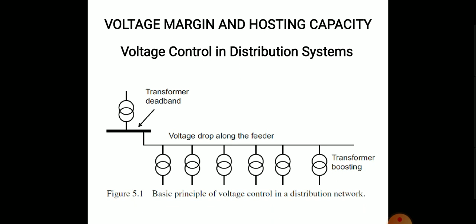So hosting capacity is the maximum amount of generation that can be connected without resulting in an unacceptable quality or reliability for other customers. In other words, maximum permissible voltage rise, that is with the connection of a distributed generation which brings maximum voltage magnitude exactly at the over voltage limit. So what is this over voltage margin, right?